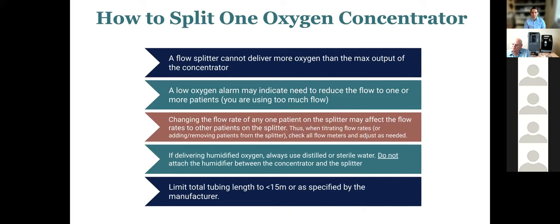So this may sound obvious, but the flow splitter does not mean that you now can deliver more oxygen than what that concentrator can put out. So if you're using a 5 liter per minute oxygen concentrator and you split it five ways, the max that any patient can get is 1 liter per minute if they're all getting the same amount. So it has to add up to the same as the total output from that concentrator. So generally this practice is going to be for relatively less ill patients or pediatric patients or neonatal patients. So just keep that in mind.